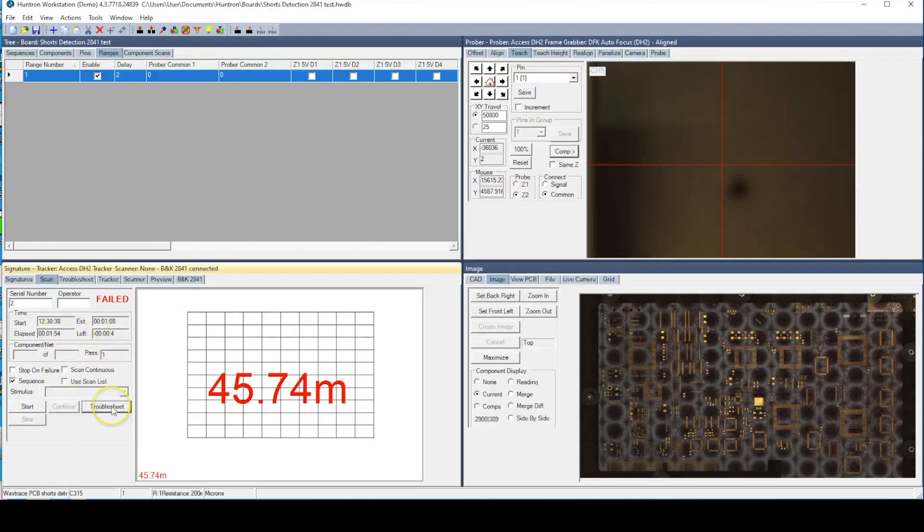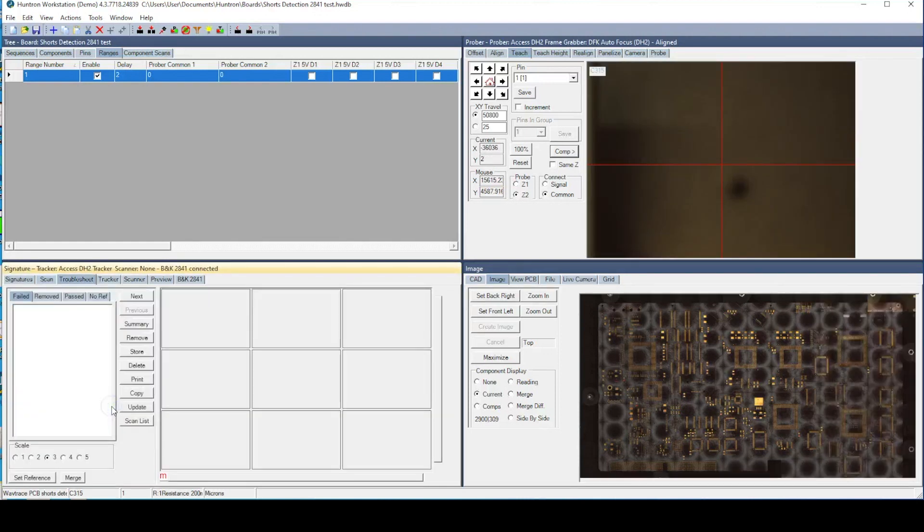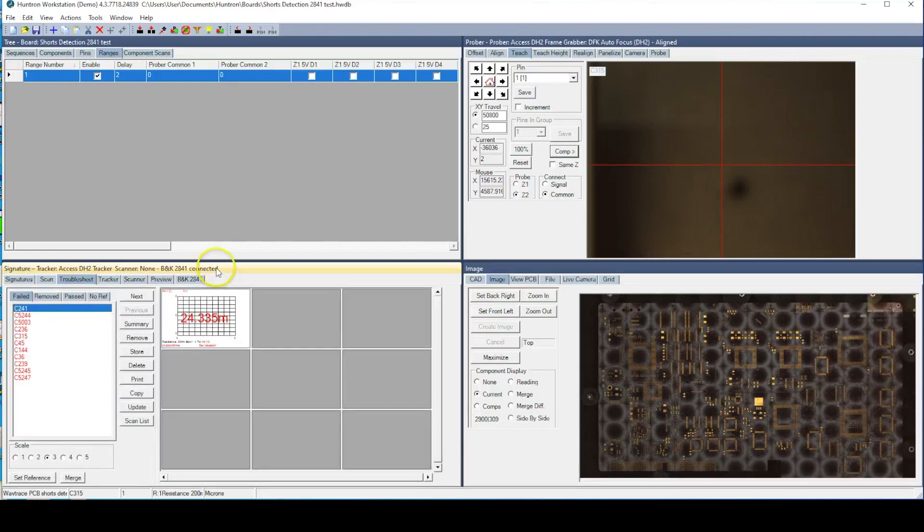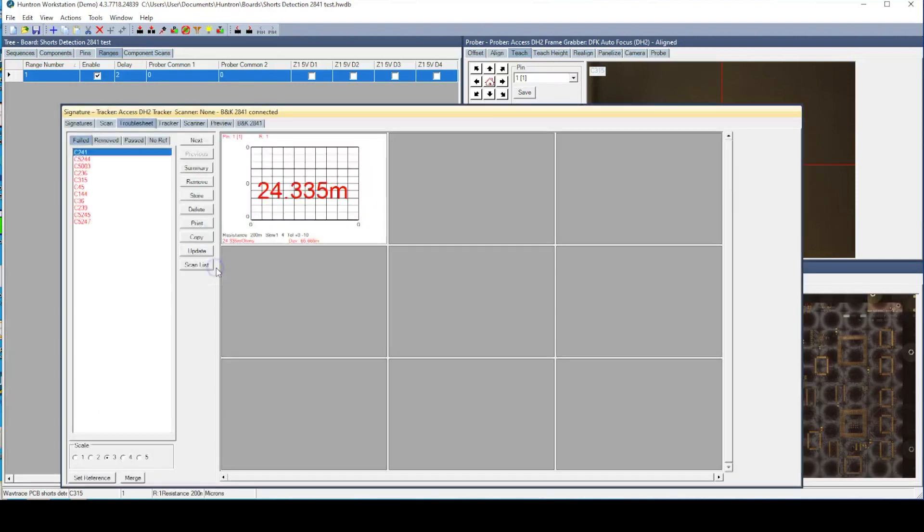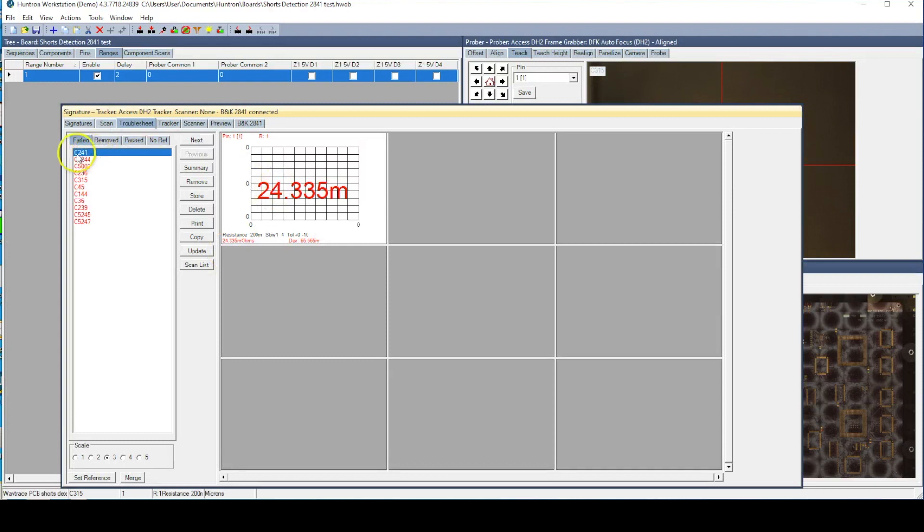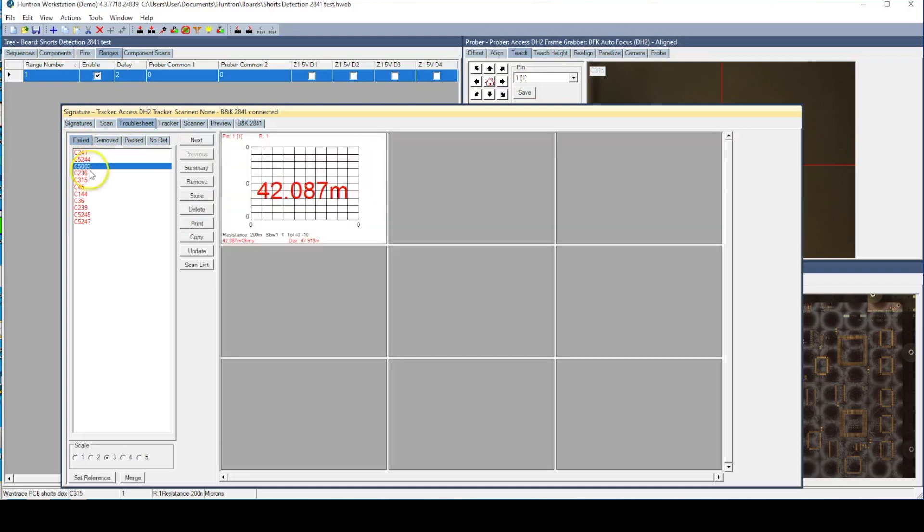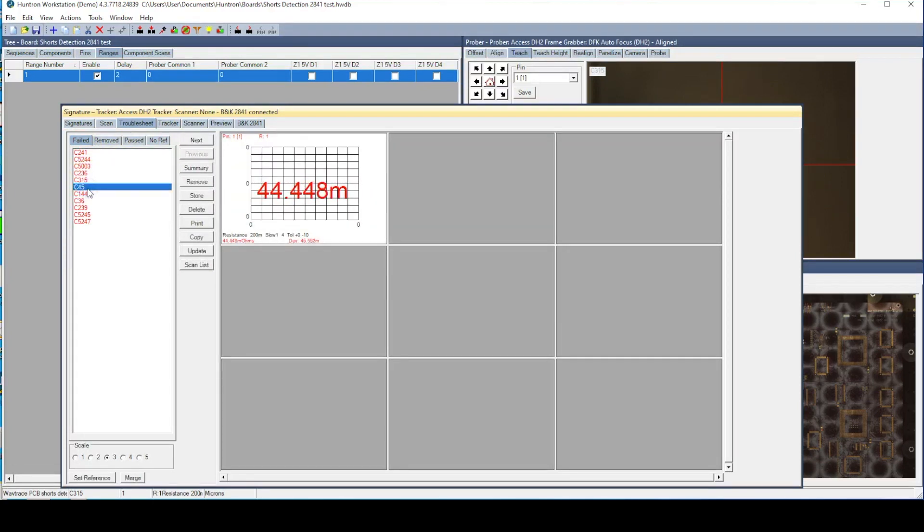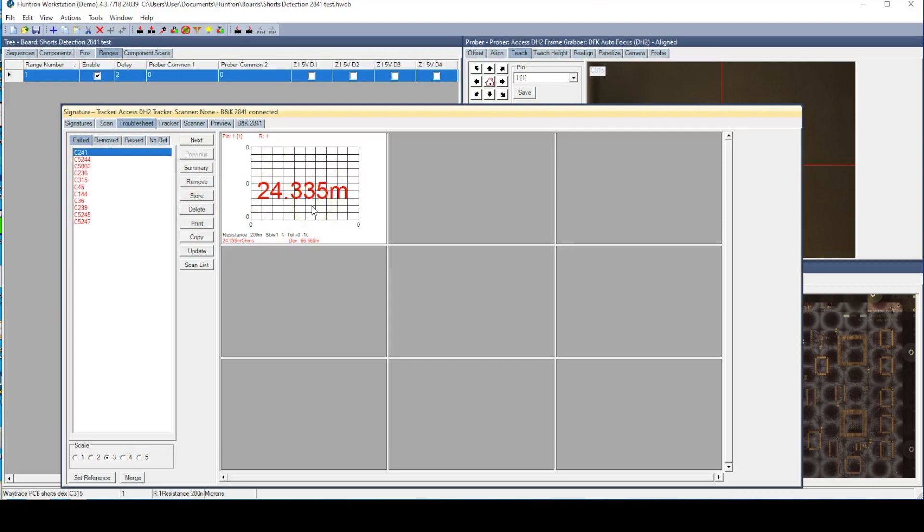The list on the left shows the failed components with the largest measurement differences at the top. Since C241 had the largest difference from our 0.1 ohm nominal value, it is listed at the top. As you look at each component down the list, you will see the resistance value get higher. C241 has the lowest value, so we can assume it is closest to the short circuit location.